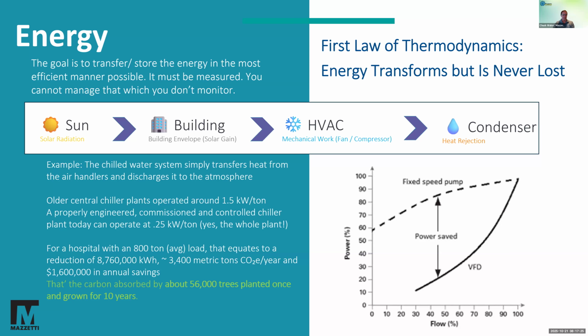To give you a quick example, when I first started commissioning or operating plants, our typical consumption was about 1.5 kW per ton for a chilled water plant. Today, we can create and operate a plant at 0.25 kW per ton. That's an 80% reduction. For an annual hospital dollar saving, that's $1.6 million if you have an 800-ton load.